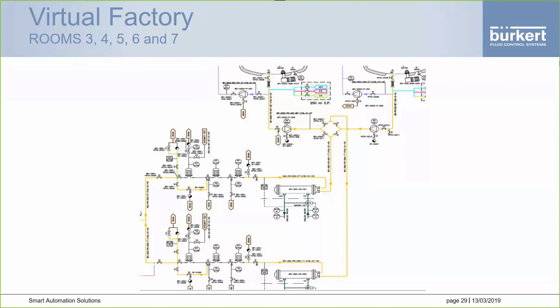I remember not that long ago when we used to use IP converters for controlling the volume of steam or even glycol through these control valves for all the heating and chilling circuits in the plant. But now it just makes so much more sense to use these newer technologies that are available to us. Now these positioners and PID controllers will mount directly into the process fitting out in the field.